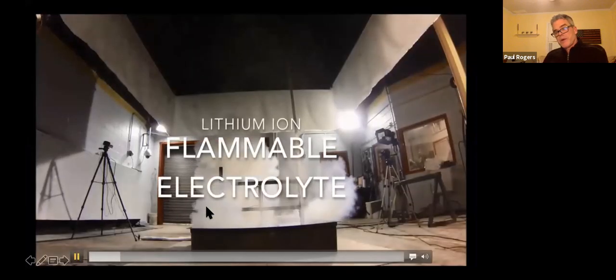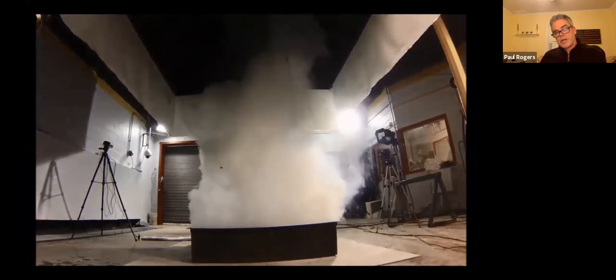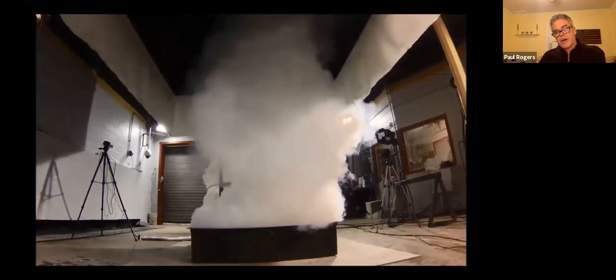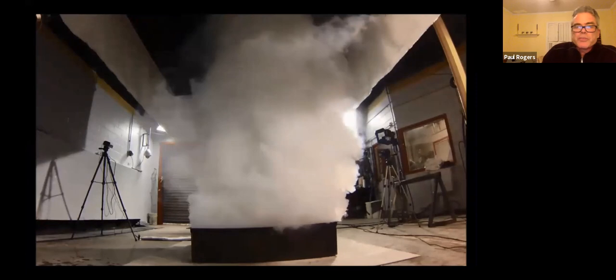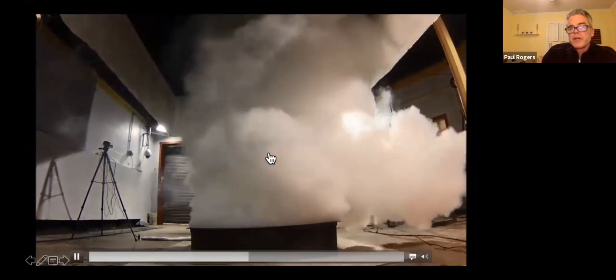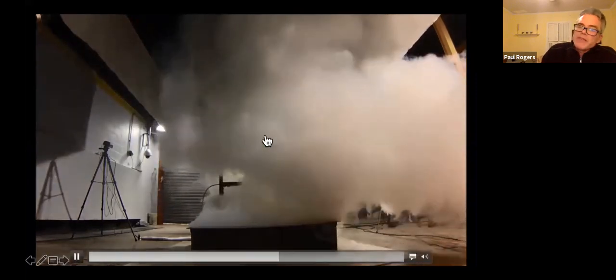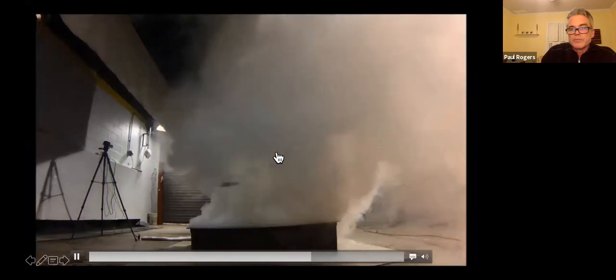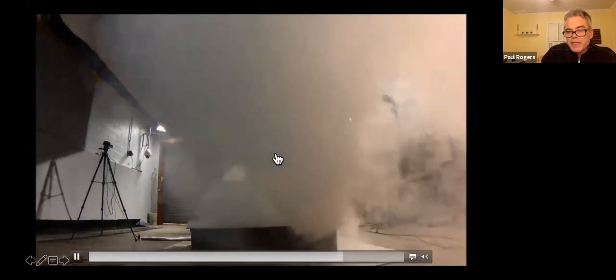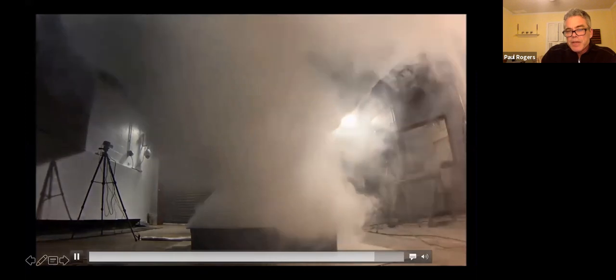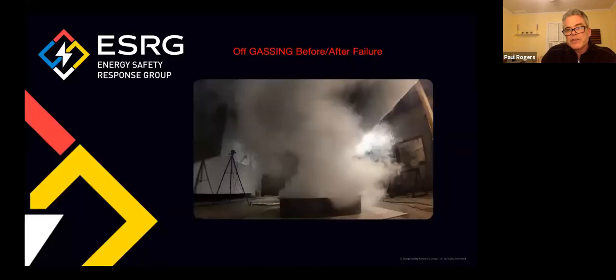So this is the module. This here is going into a failure, and you see all this smoke here. This is flammable gas. Someone might say, oh wow, look at flammable gas. Think of this being propane inside a room. What are we missing here? An ignition source. And then what? Then we're going to have some sort of deflagration. So that is a concern.